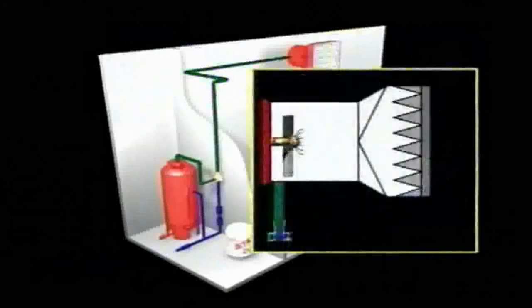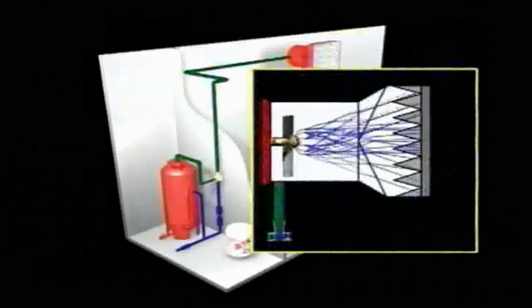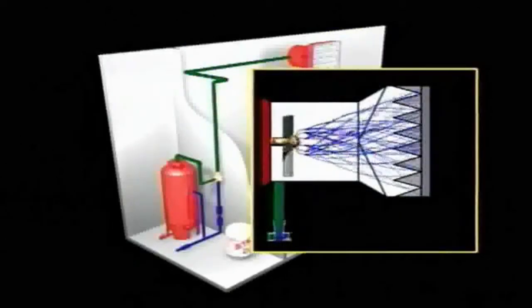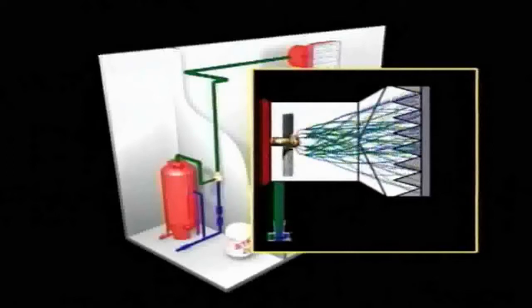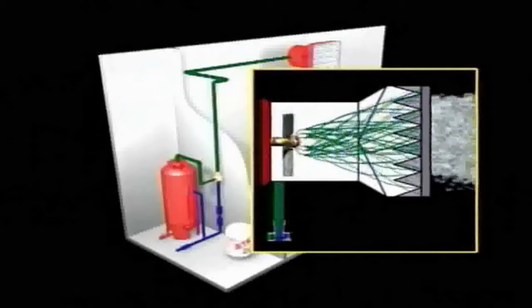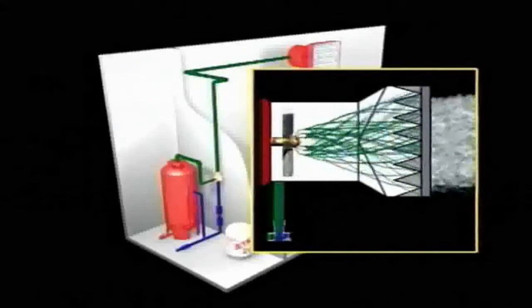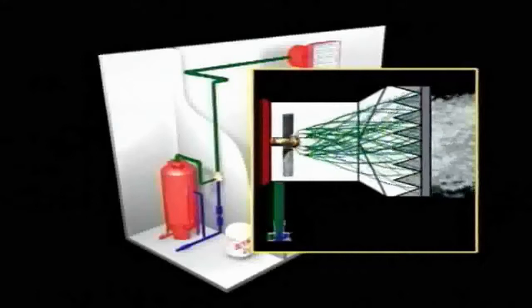The foam solution is routed from the proportioner outlet to one or more high expansion generators located in the hazard area. Within the foam generator, rotating nozzles spray the solution onto a perforated screen in a circular pattern. Simultaneously, the water-driven fan blows a high volume of air onto the same screen, producing the expanded foam.